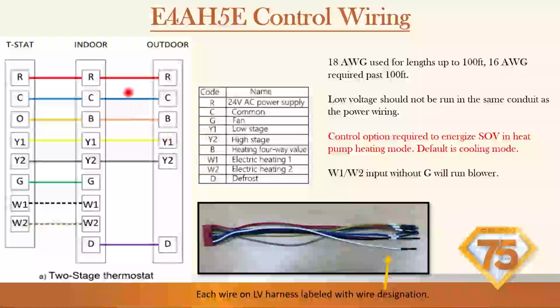Control wiring is what we're all used to. You've got your red 24 volt, your common, T-stat O reversing valve, indoor B2B. This is important though. With all Trane and American Standard, we're used to the reversing valve energizing in cooling. This one is a heating 4-way. So a control option is required to energize the switchover valve, reversing valve, in heat pump heating mode. So in heating, we energize the 240 volt reversing valve. So keep that in mind. It's a 240 volt reversing valve, not a 24 volt.